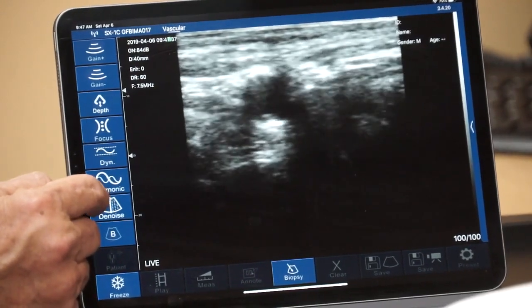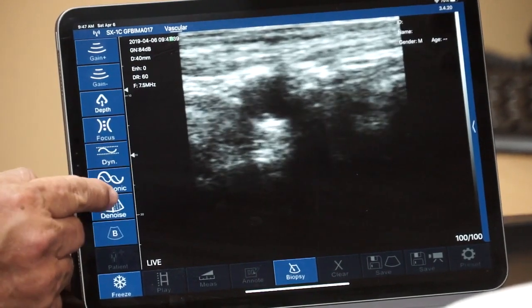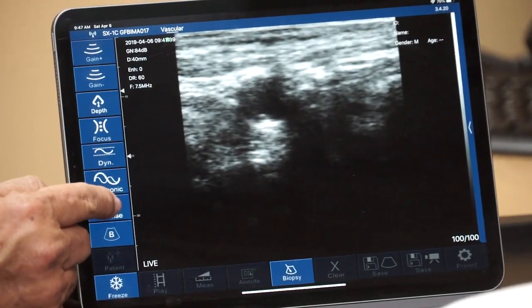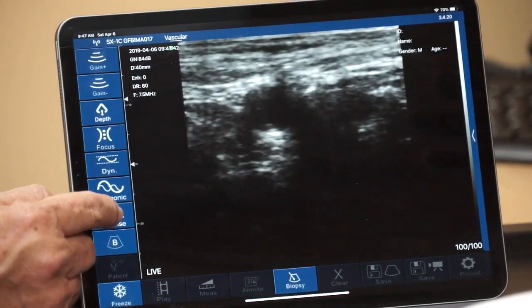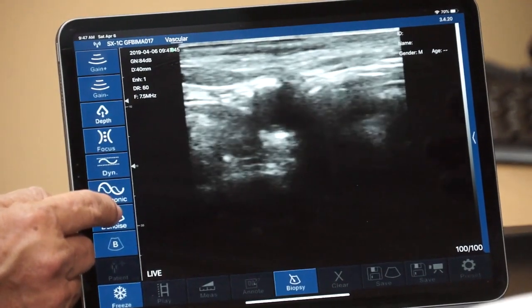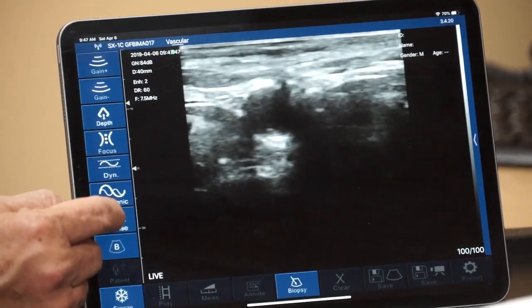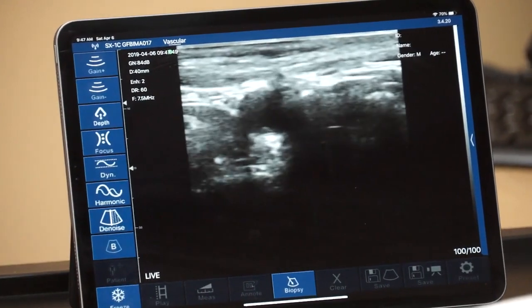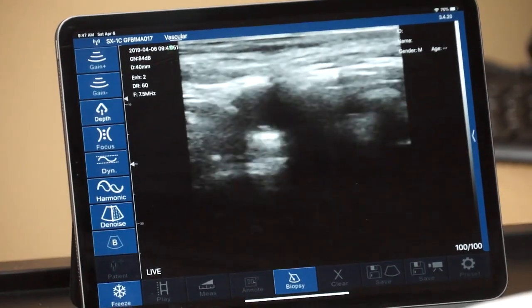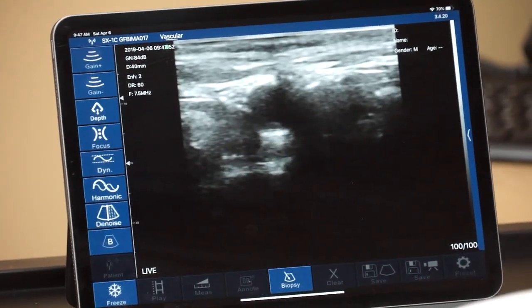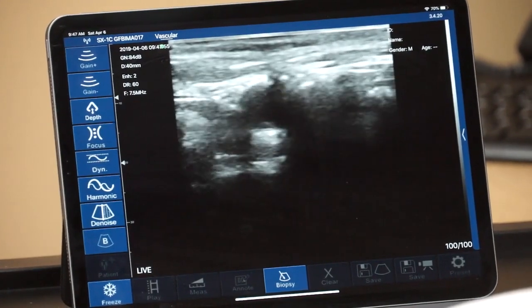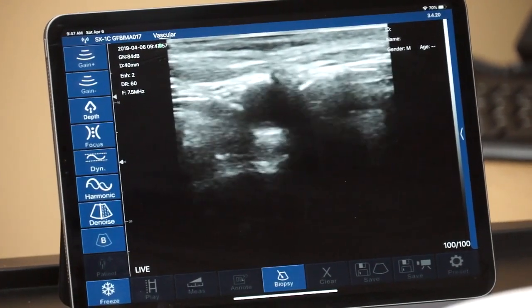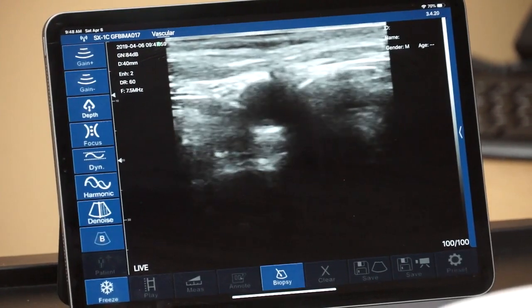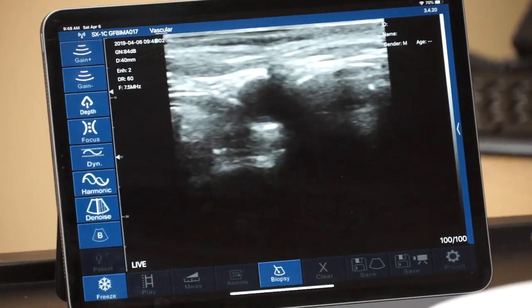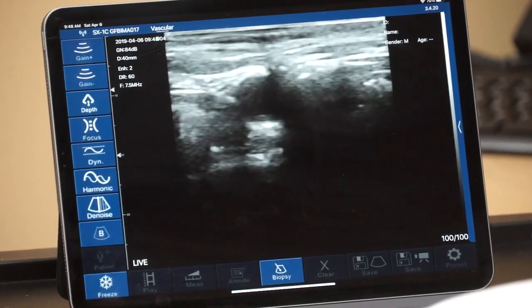Now you can see this is full of artifact and noise in the returning echoes. As we increase our filtering just a little bit, the image softens. Up one more. A typical value for scanning is somewhere in the middle of that range, around level 2 for filtering. Based on your needs and the target, you can adjust the filter and eliminate more or less clutter out of the echoes.